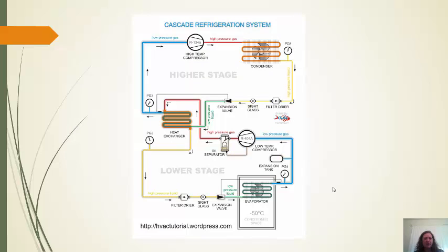Cascade refrigeration is another really important thing to consider. What a cascade refrigeration system is able to do is take a refrigeration need where maybe the low and high temperature extremes are just too great for any one working fluid. So I can use one working fluid as low as I can get it, and then switch to a different, maybe more expensive working fluid to complete the refrigeration cycle. And again, what you'll notice is that the pairing always happens at a heat exchanger. So the heat out from one goes into another. And this is, like I say, a great way to achieve really extreme temperature differences when one fluid is just simply not going to work. And you know everything needed to analyze something like this because it's just two different refrigeration systems coupled with an equation that says the heat out here is equal to the heat in here at the heat exchanger.